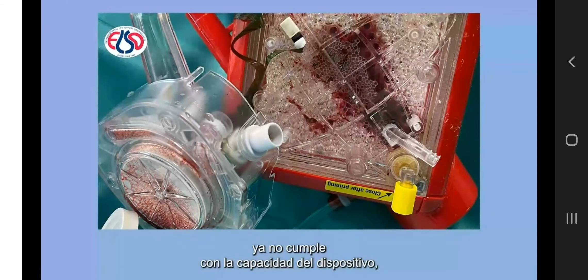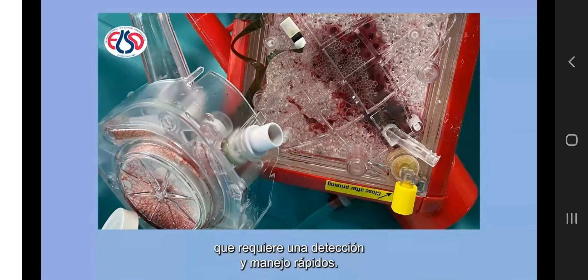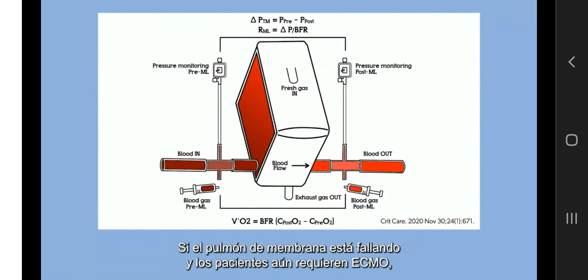Measured gas transfer no longer meets the capacity of the device. Membrane lung failure, resulting in decreased or completely absent extracorporeal support to gas exchange, is a potentially life-threatening ECMO complication requiring prompt detection and management. If the membrane lung is failing and the patient still requires ECLS, you may need to replace the device. How do you decide whether to replace the membrane lung or wait?